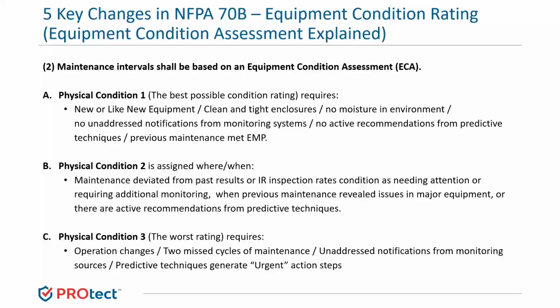For your physical condition 2, that's going to be assigned where any of the following apply. That can be where your maintenance results deviate from past results, or indicate that a more frequent maintenance interval is required. This would include scenarios where previous maintenance activities revealed that the component needed repair or replacement of any major components with that equipment. If there have been any notifications from the continuous monitoring system since the last assessment, that automatically puts it into a condition 2 category. And any predictive maintenance techniques that generate active recommendations would also bump this into a condition 2 category.